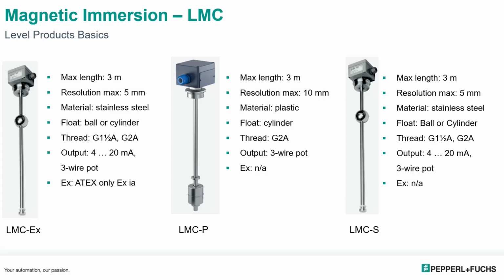The LMCP is a plastic version. Again, the maximum length is 3 meters. However, the resolution on this is 10 millimeters. So every 10 millimeters, you'll get an update of where the level is. It's plastic. You can only get the cylinder. It's restricted on the number of types of threads or process connections you can get. We do have the G and the NPT threads on there. And you can get this with a 3-wire potentiometer output. And then we have the LMC-S. This is very similar to the LMC-EX, except it doesn't have the intrinsically safe certification.